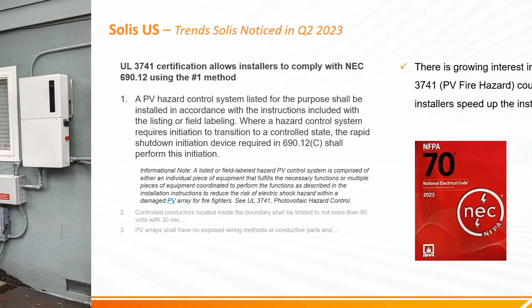Another big thing we're noticing is more interest in this UL 3741 certification. This certification allows you to use method 1 in 690.12, rapid shutdown under the National Electrical Code, as opposed to method 2, where controlled conductors located inside the array boundary shall be limited to not more than 80 volts within 30 seconds. We're talking about rapid shutdown receivers up on the roof on every module complying with rapid shutdown using method 2.